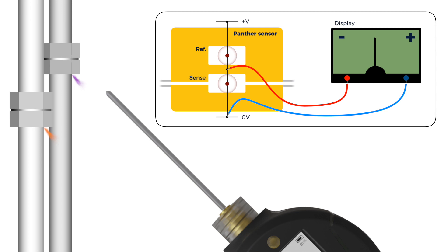This video outlines how the thermal conductivity sensor within the Panther works. Two microthermister beads are housed in a temperature-stable block that remains at ambient temperature. Both microthermister beads are powered so generate heat which dissipates through an air gap to the block at a constant rate.